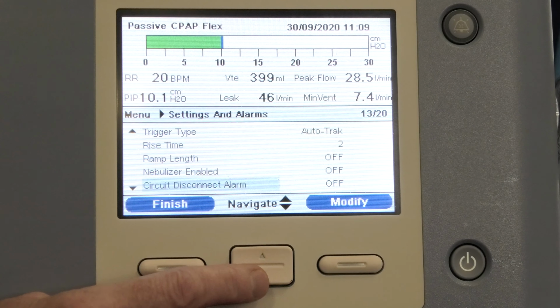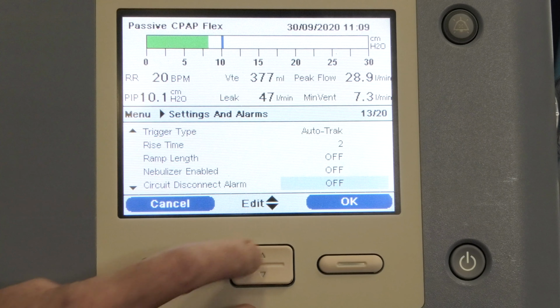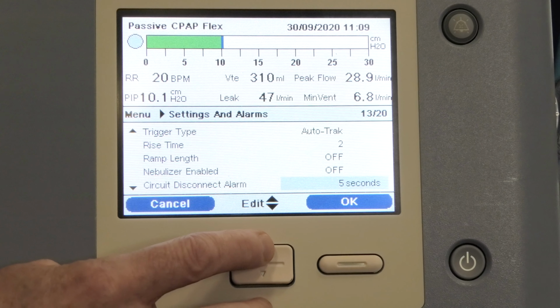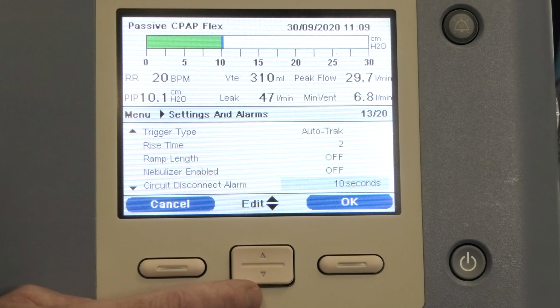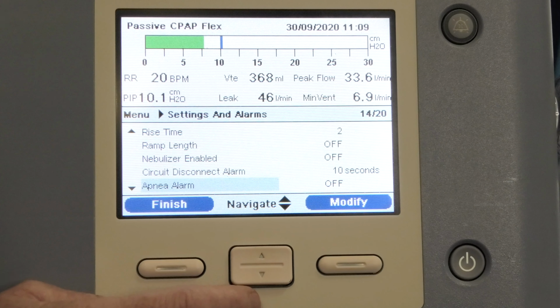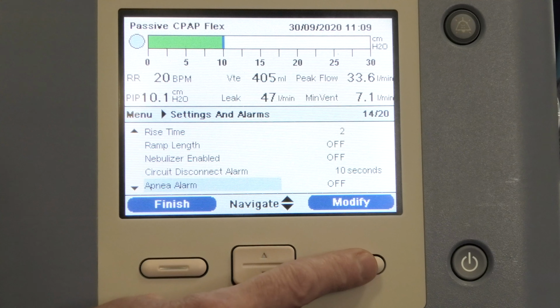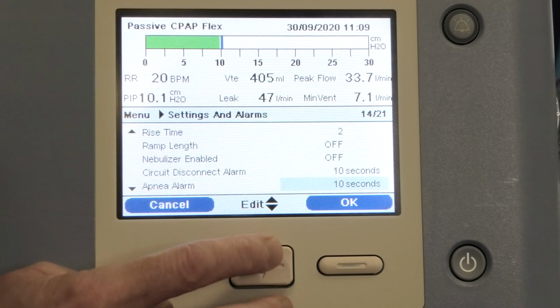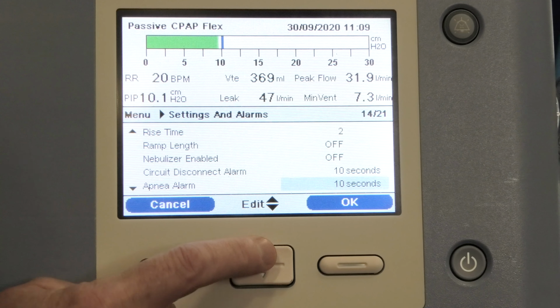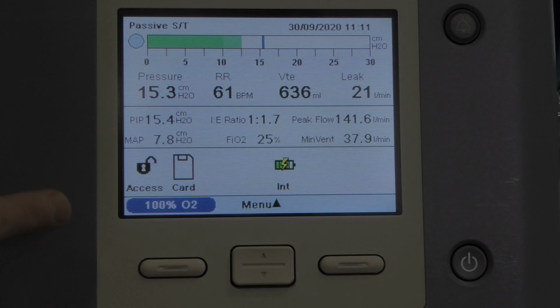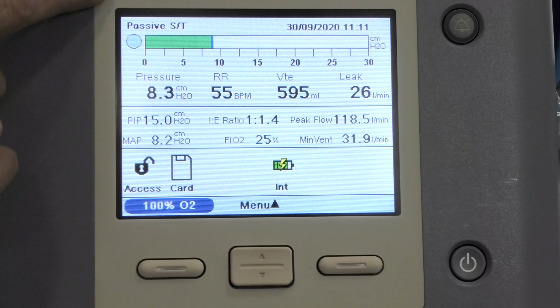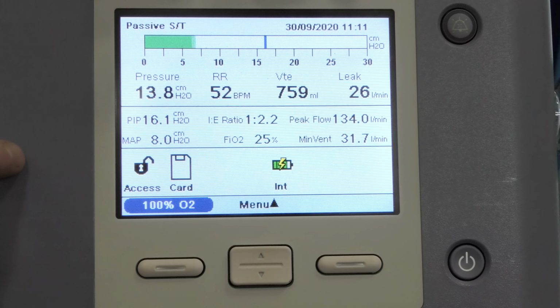Leave our ramp off, circuit disconnect, edit. You probably want to know within 5 or 10 seconds whether your circuit is disconnected, and we want to turn our apnea alarm on. So again, modify, change our apnea alarm to 10 seconds. We can see now that we're in passive ST, which is our BiPAP screen.